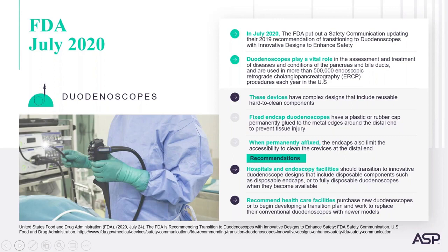Fixed end cap duodenoscopes have a plastic or rubber cap permanently glued to the metal edges around the distal end to prevent tissue injury from the metal edges of the scopes. When permanently affixed, the end caps also limit the accessibility to clean the crevices at the distal end. The FDA recommendations: FDA has asked each duodenoscope manufacturer to transition away from fixed end cap duodenoscopes to those with more modern design features that facilitate or eliminate the need for reprocessing.